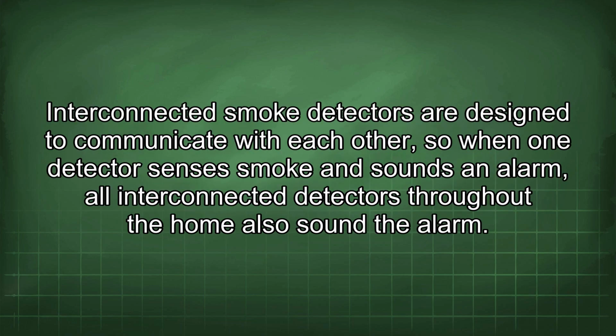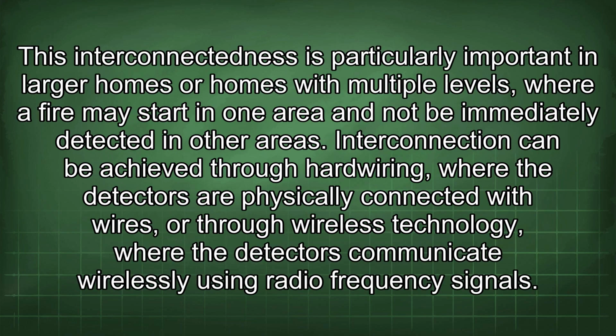Interconnected smoke detectors are designed to communicate with each other, so when one detector senses smoke and sounds an alarm, all interconnected detectors throughout the home also sound the alarm. This interconnectedness is particularly important in larger homes or homes with multiple levels, where a fire may start in one area and not be immediately detected in other areas. Interconnection can be achieved through hardwiring, where the detectors are physically connected with wires, or through wireless technology, where the detectors communicate wirelessly using radio frequency signals.